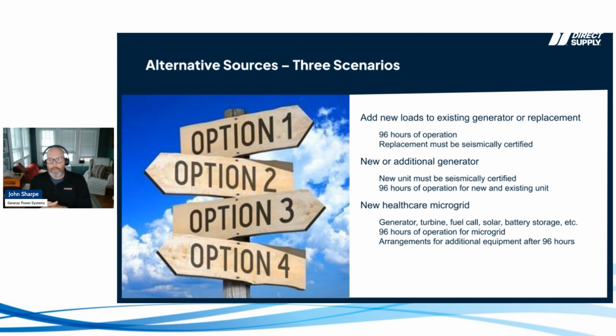Or I could add a completely different generator to the facility. This could be the generator that takes care of these newly mandated loads. So you'd size that up, how big of a generator do I need, and make sure that generator carries these particular loads and is good for 96 hours.